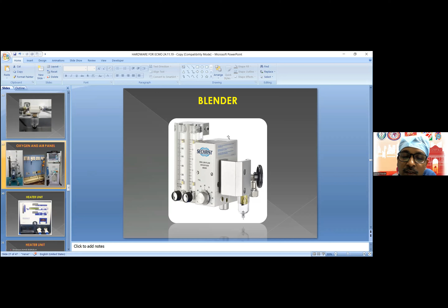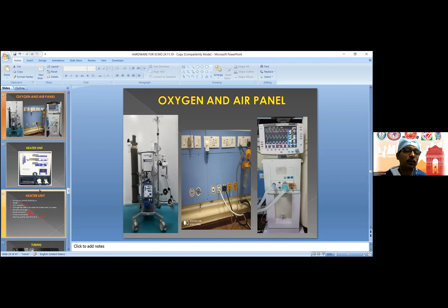Oxygen and air connection. Previously, we used only a ventilator when a patient was sick. When the patient is so sick that we are not able to manage with the ventilator alone, we use the ventilator and ECMO simultaneously, and then more sources of oxygen and air connection are required in the system. That we have to remember. Most ICUs provide only two oxygen connections and one air connection, so we may have to think of this and introduce it into the system.